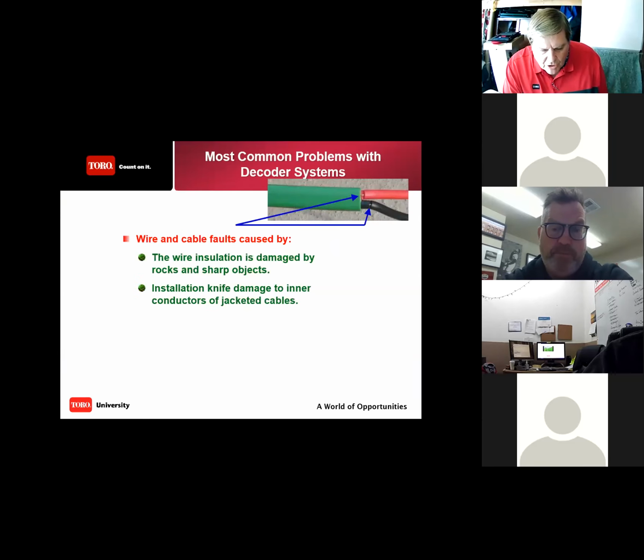Looking here, when you're cutting the outer insulation on the 2-wire path, be careful not to cut into the wire inside it. A proper connector or proper wire cutter is critical. They sell a device called a jacket stripper. A jacket stripper has a vertical blade that cuts parallel to the wire, not across it, so it cuts just lightly into it, and you can peel it open to get to the wires.